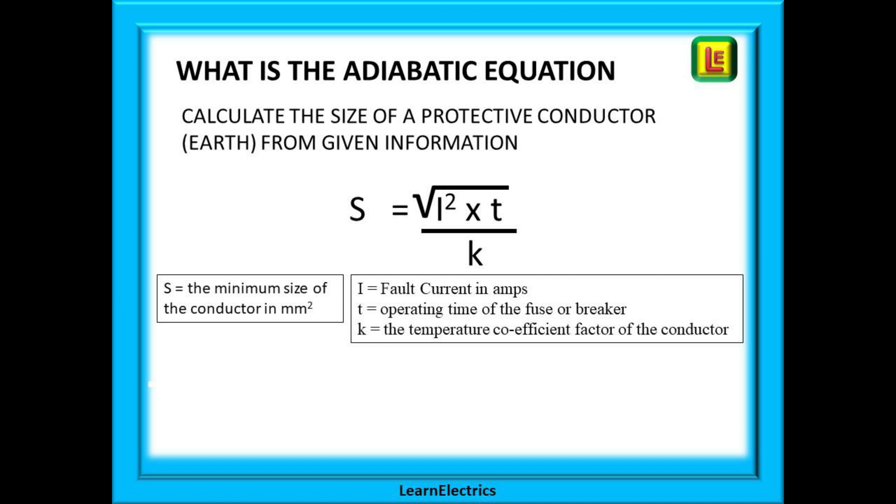It is very easy to interpret the formula. S is the size or cross sectional area of the conductor. This is what we want to know and this is found by inserting the other three parameters that are shown into the formula. We need to know the fault current, the operating time of the fuse or breaker and this thing called K, the cable factor.